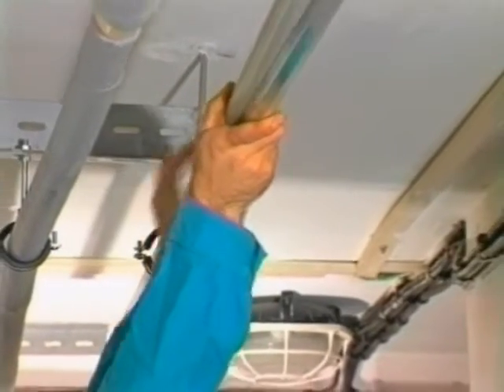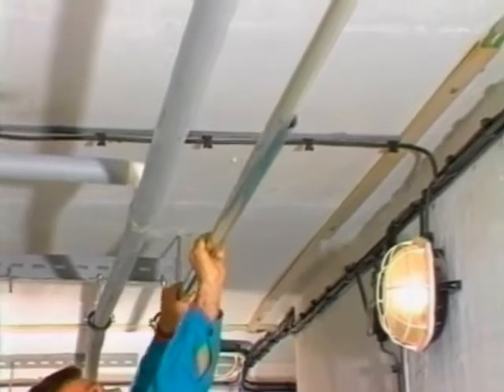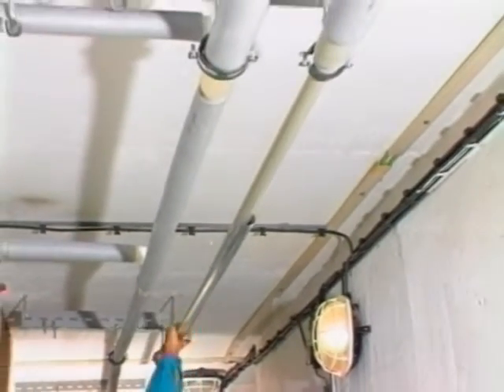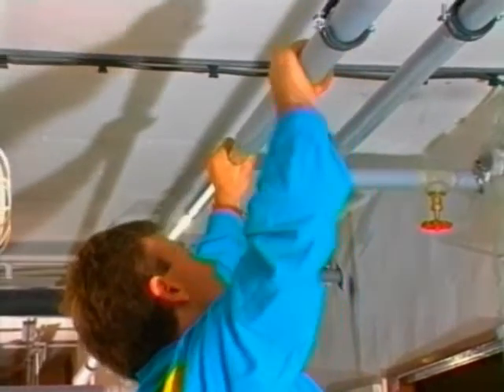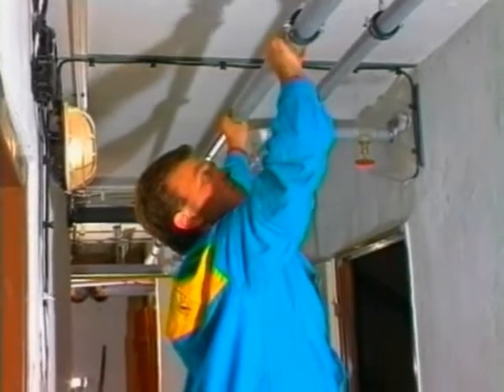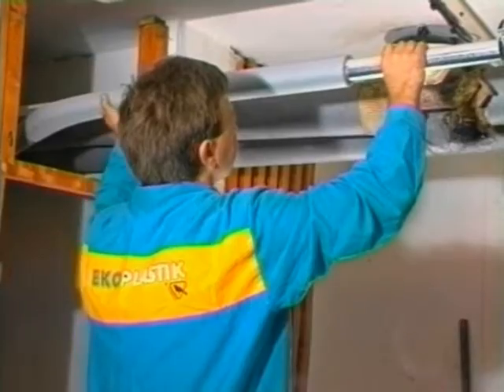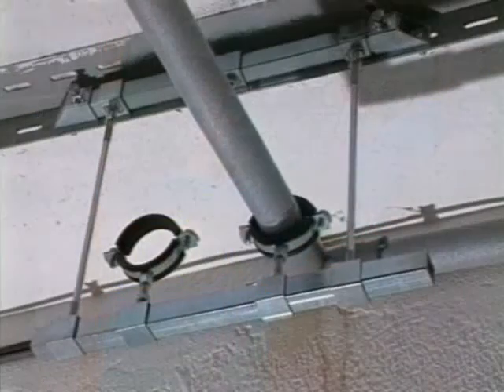Horizontal pipes are best run along a galvanized supporting trough. It increases the firmness of the pipe system and allows for greater distance between supports. The pipes and trough are insulated and fitted into a sleeve. This type of installation looks very pleasing. Fittings which are mounted on the piping system must be properly supported so that their weight isn't borne by the pipes.